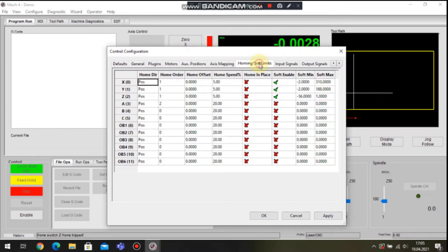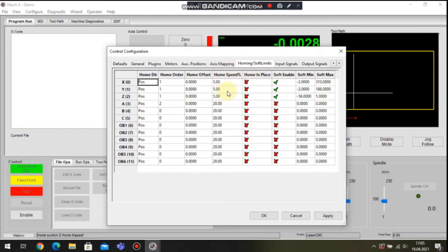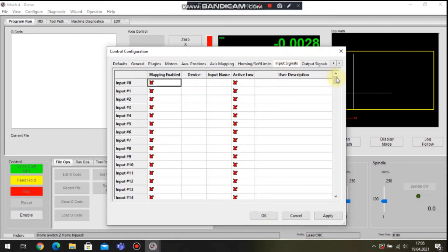In the next tab we can set up the homing and software limits for each axis. The parameters like home speed, soft enable, home in place can be set exactly here.